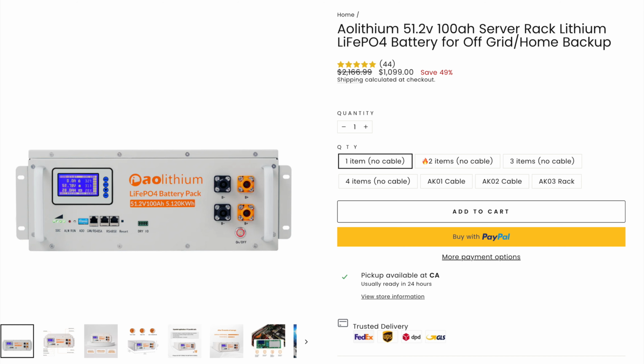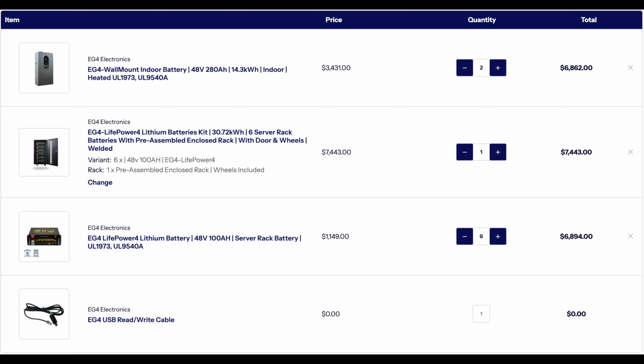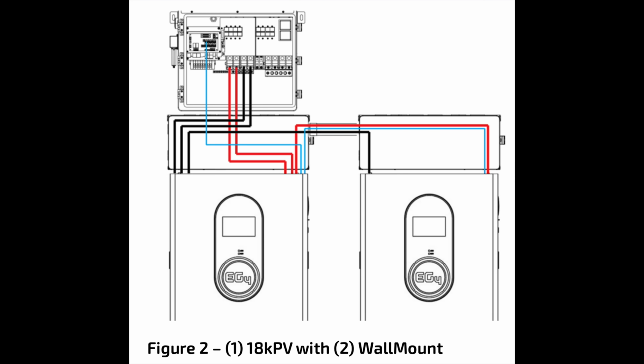Yes, the server rack batteries will have a little more capacity, but you'll also have more failure points or connections, since each battery needs a connection. Say each battery has 2 connections, or 3 if you're doing communications — 3 times 6 is 18 connections you'd have to tie in. But with 2 of these in parallel, you only have 2 connections, or 3 with communications. That's probably the biggest differentiating factor, besides the 2 kilowatt hours of capacity.